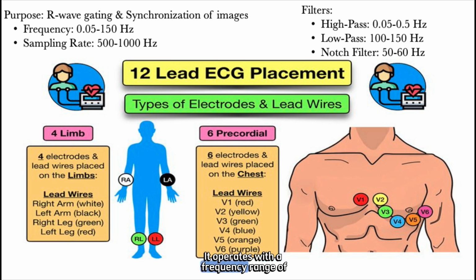It operates with a frequency range of 0.05 to 150 Hz and a sampling rate of 500 to 1000 Hz, ensuring accurate cardiac event capture. The 12-lead ECG system includes 4 limb electrodes and 6 precordial leads to provide full cardiac electrical mapping.